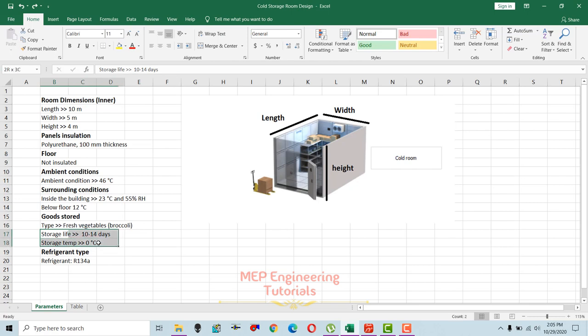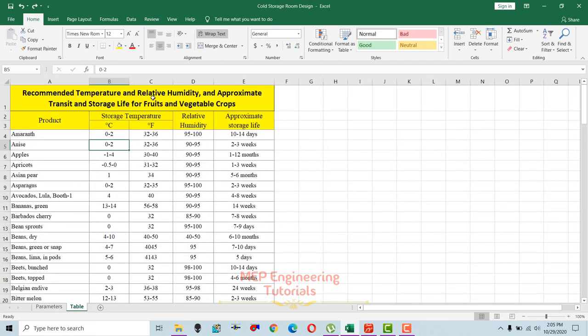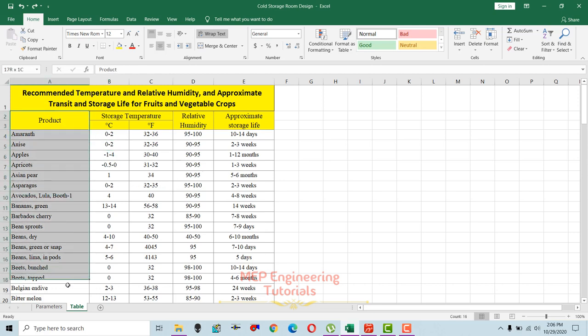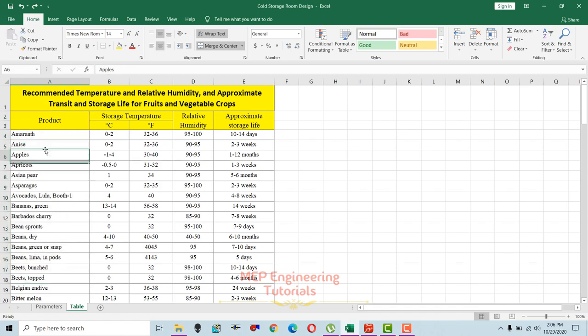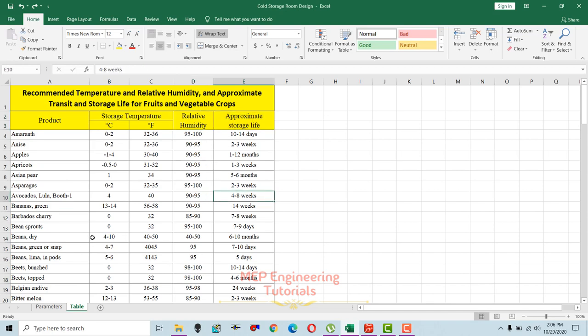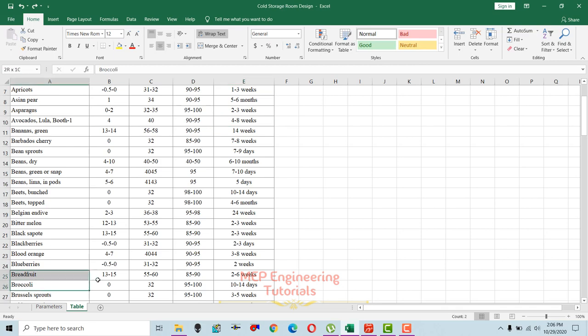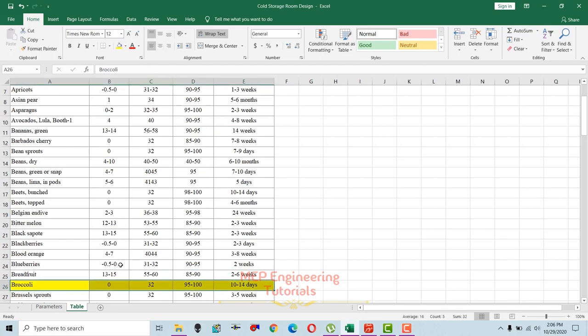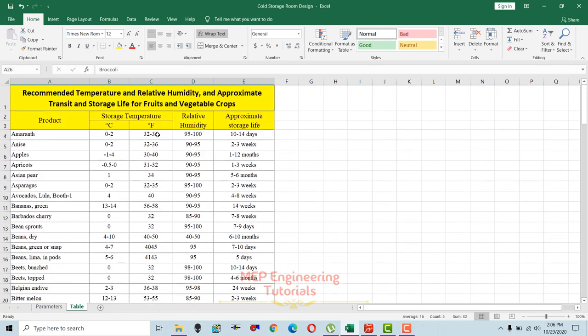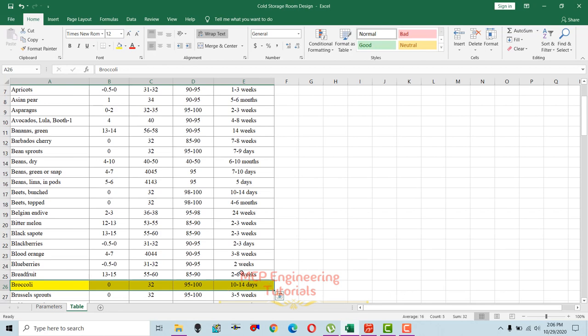Storage life and storage temperature data can be found in a reference table — recommended temperature, relative humidity, and approximate storage life of fruits and vegetables — provided by the agricultural department, arranged alphabetically. For broccoli, the storage temperature is 0 degrees Celsius (32 degrees Fahrenheit), relative humidity is 95 to 100 percent, and approximate storage life is 10 to 14 days — maximum two weeks.